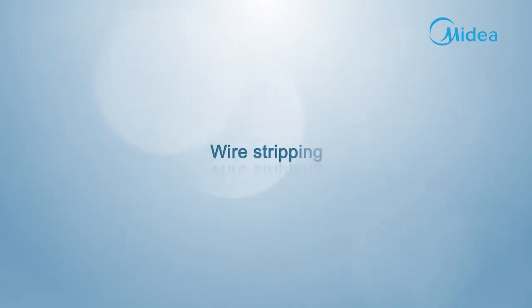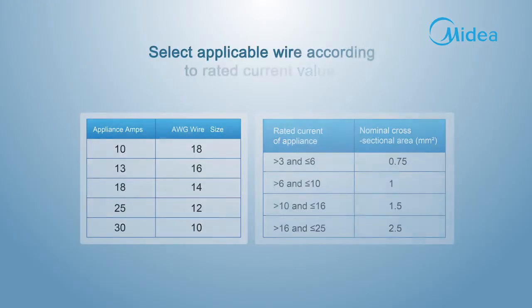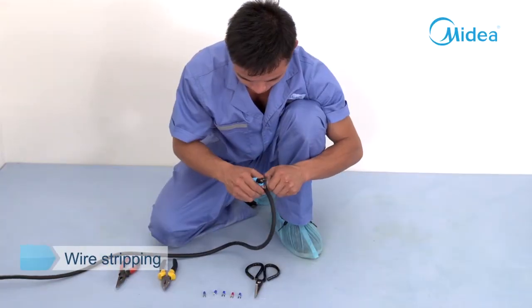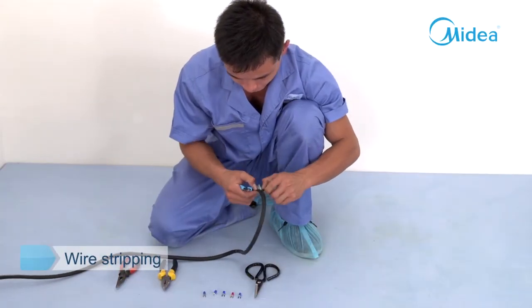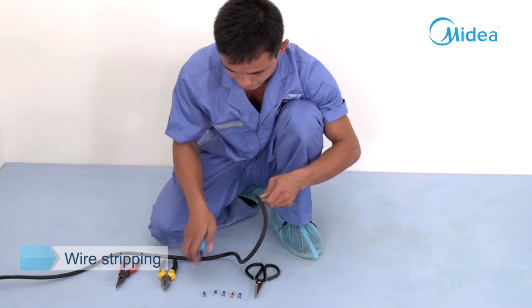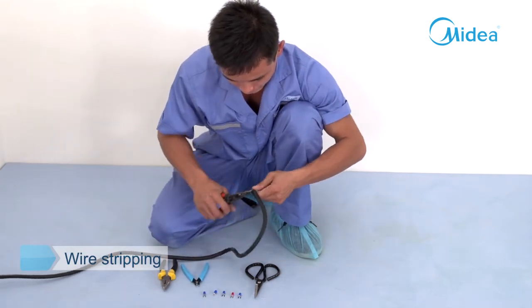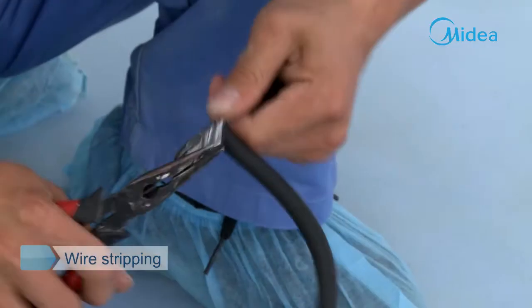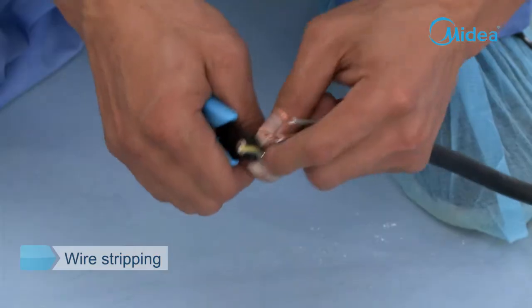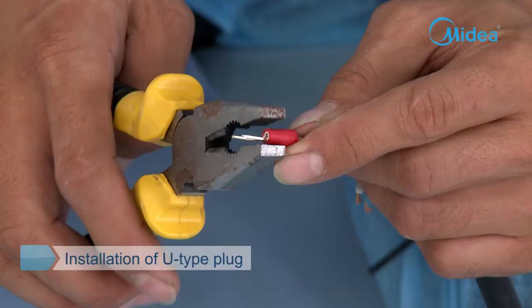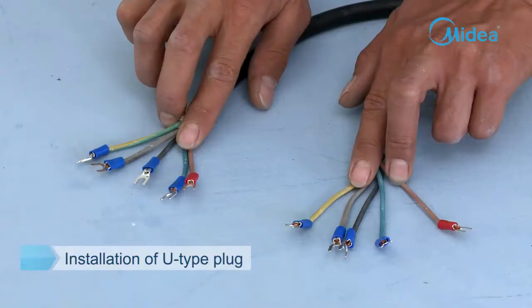Wire stripping. Select applicable wire according to the rated current value; two common specifications are shown in the figure. Strip the rubber skin at both ends of the connecting wire to uncover the wire core. Use a wire stripper to strip the wire core. Use a wire crimper to clamp the U-type plug, and pay attention to distinguish the L-wire from other wires.